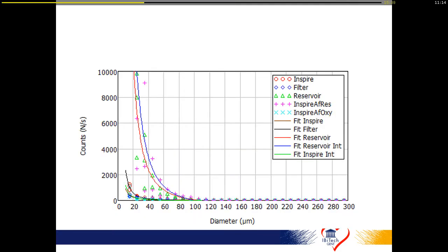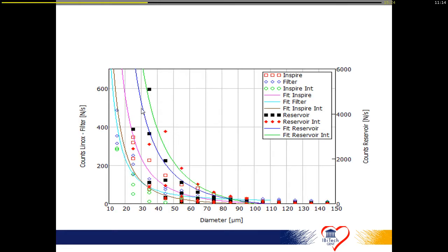We can also question, what is the best, integrated or non-integrated? So here you can see exactly the same slide, but this time we have a separate filter with the same unit, and then we have the integrated version. Let's enlarge it again. And as you can see, both filters are actually performing exactly the same. So that's not the issue. The only benefit of the integrated system is the correct positioning, but in efficiency, it's exactly the same.